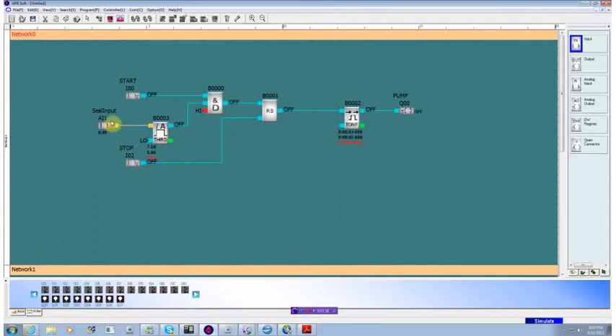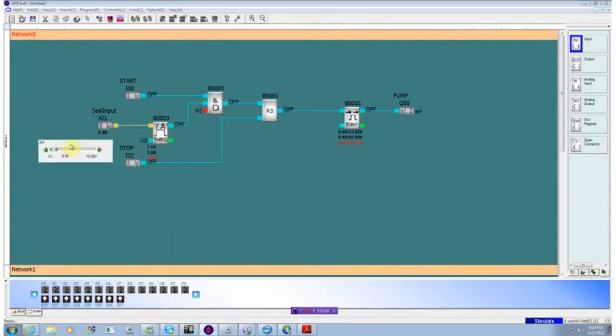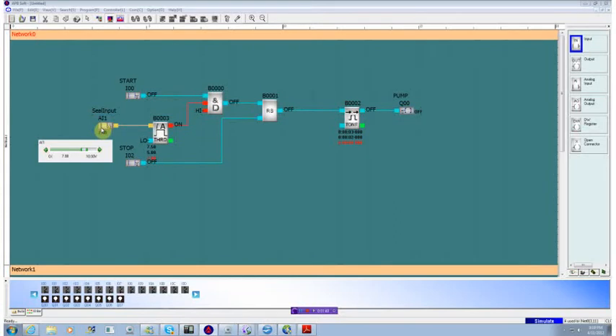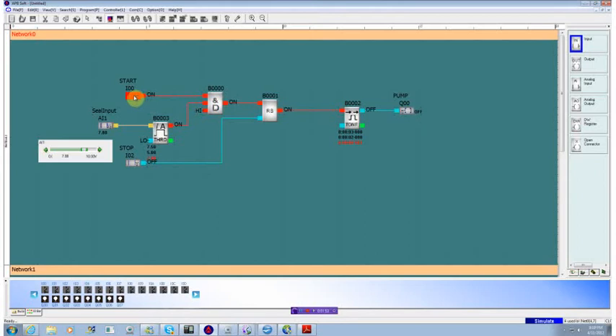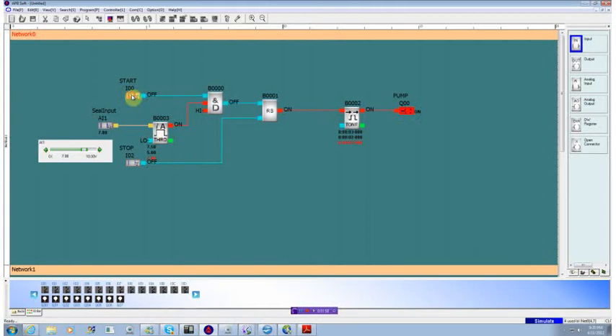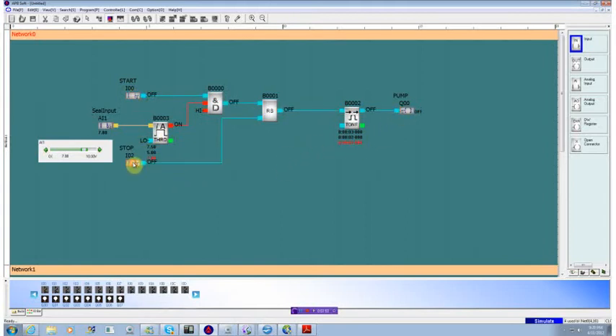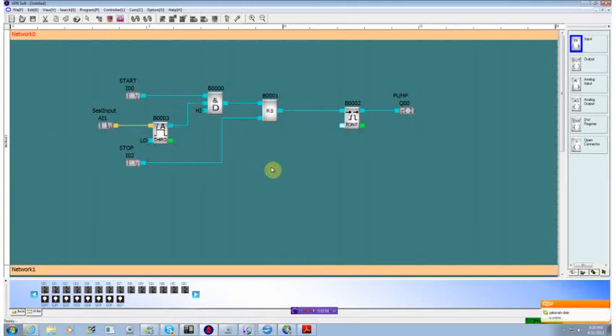What we want to do is take a look at some of this in operation. We'll run our simulator. We see that we have an analog set point that must be above 7.5. That's detecting a low resistance on the seal leak detector. Provided that input's on, when we hit the start, we time down for 3 seconds to turn on the pump. And then when we hit the stop, we time down for 2 seconds to turn off the pump.